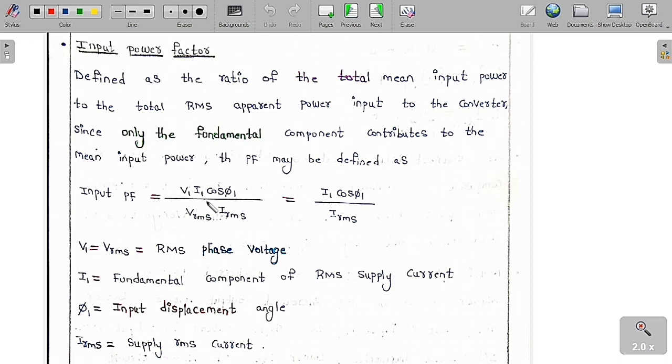Input power factor is equal to V1 I1 cos phi 1 divided by VRMS into IRMS, where V1 is the RMS value of the fundamental voltage, I1 is the RMS value of the fundamental current, and phi 1 is the phase angle between the fundamental voltage and the fundamental current. Because V1 and VRMS are the same, they cancel, so finally we get I1 cos phi 1 by IRMS. Here cos phi 1 is called the fundamental displacement factor, whereas I1 by IRMS, the RMS value of the fundamental component over the RMS value of the overall current, is called the distortion ratio.